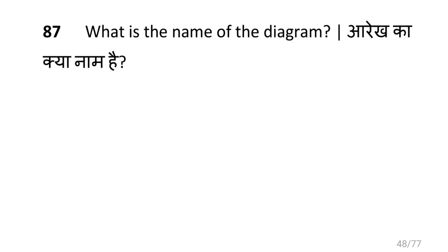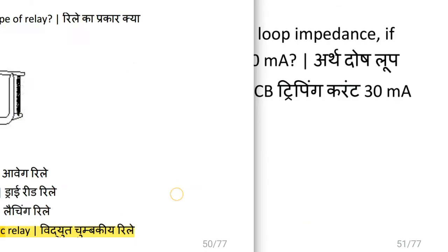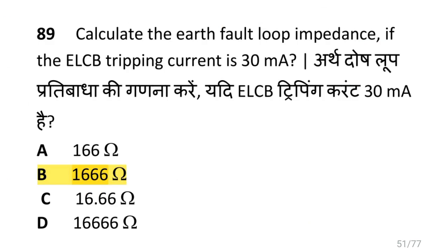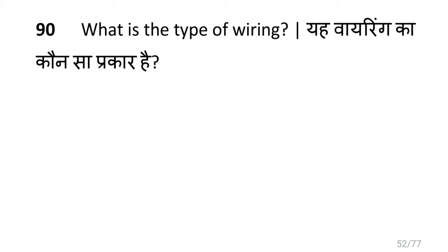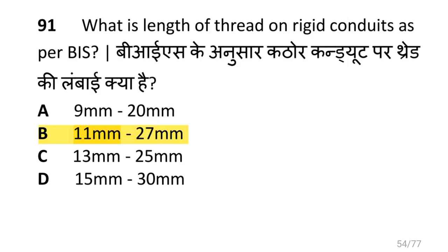What is the name of this diagram? That is staircase wiring. What is the type of relay? That is electromagnetic relay. Calculate the earth fault loop impedance if the ELCB tripping current is 30 milliampere. Then the earth fault loop impedance will be 1666 ohms. What is the type of wiring? That is cleat wiring. What is the length of thread on rigid conduit as per BIS? That is 11 mm to 27 mm.